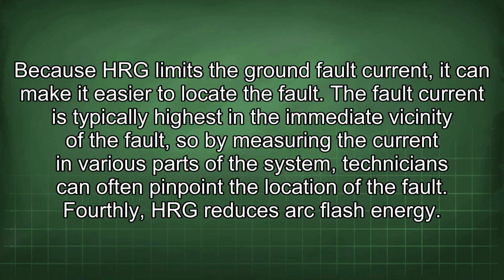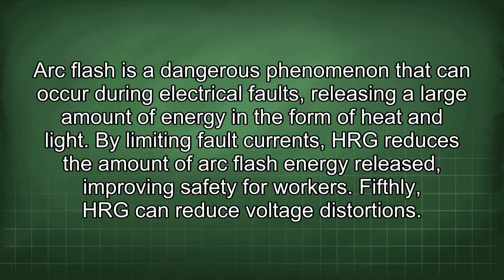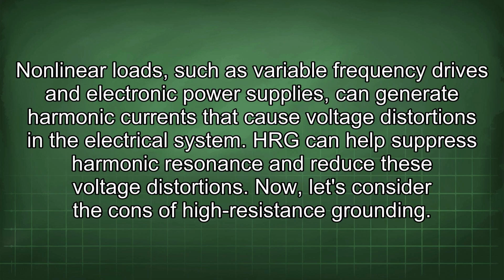Fourthly, HRG reduces arc flash energy. Arc flash is a dangerous phenomenon that can occur during electrical faults, releasing a large amount of energy in the form of heat and light. By limiting fault currents, HRG reduces the amount of arc flash energy released, improving safety for workers. Fifthly, HRG can reduce voltage distortions. Nonlinear loads such as variable frequency drives and electronic power supplies can generate harmonic currents that cause voltage distortions in the electrical system. HRG can help suppress harmonic resonance and reduce these voltage distortions.